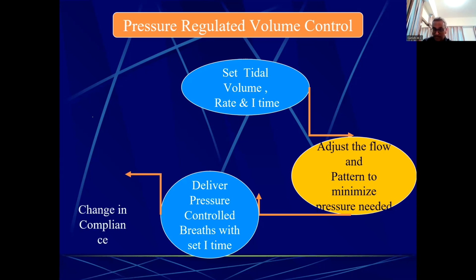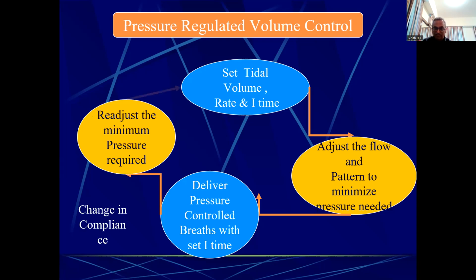This is one of the common modes I use personally because it achieves both pressure regulation as well as volume control. It readjusts the minimum pressure. The algorithm is similar to volume support, but volume support you use in a patient who is spontaneously breathing, whereas pressure regulated volume control is something you use in a patient who is not spontaneously breathing, or when you have just intubated. In fact, Maquet ventilators have something called volume support / PRVC. That means as long as the patient is not breathing spontaneously, it will be PRVC. The moment the patient breathes on his own, it will switch to volume support. It's called dual mode. Make sense?